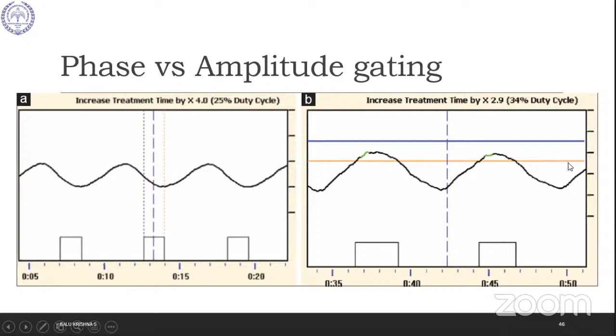Here it shows you each kind of technique and how much extra time it takes. If you are using phase gating, switching on and off for each respiratory cycle, it takes 4 times the beam-on time that is needed for a regular treatment. The difference with amplitude gating is only 3 times. The system itself will tell you this, and you can choose accordingly.